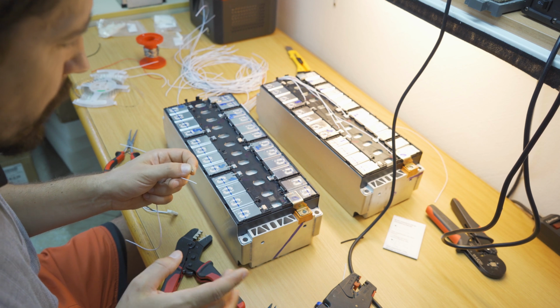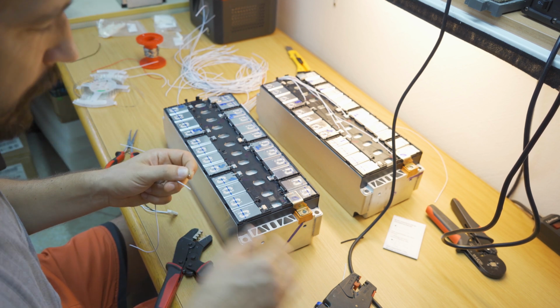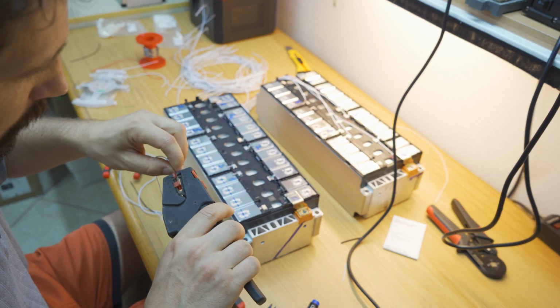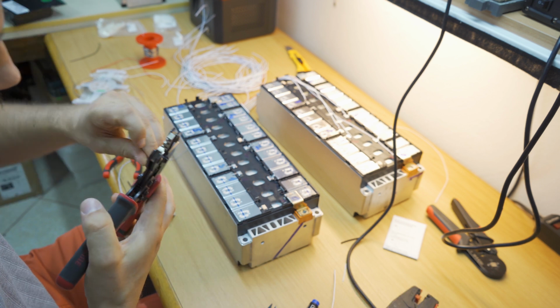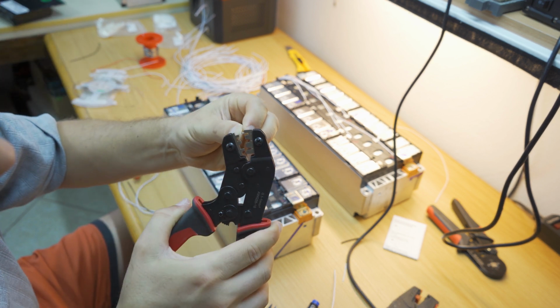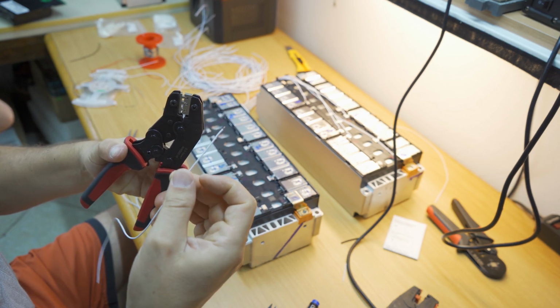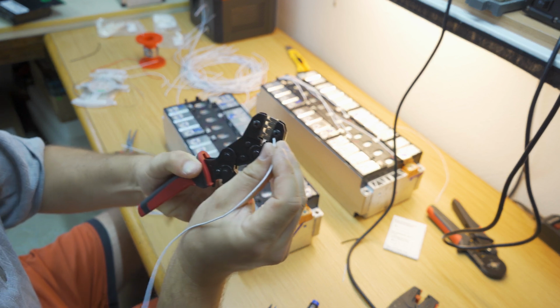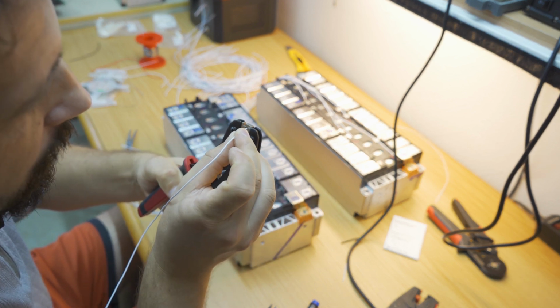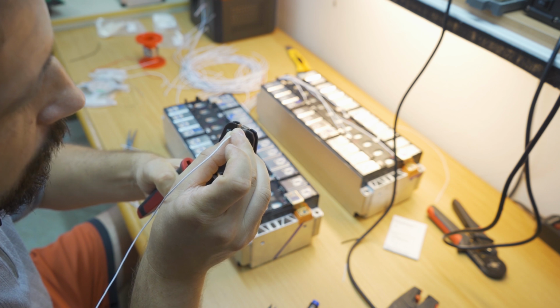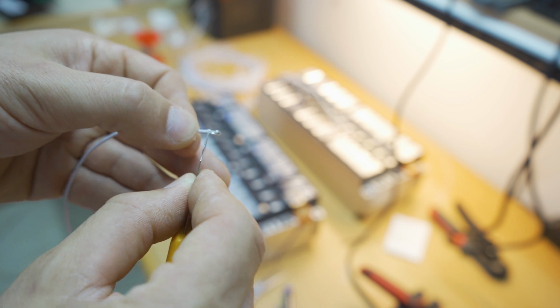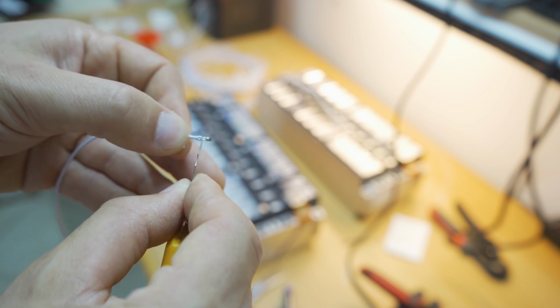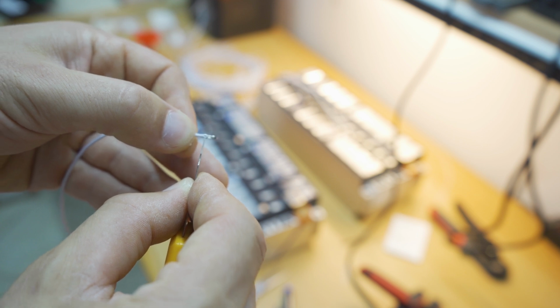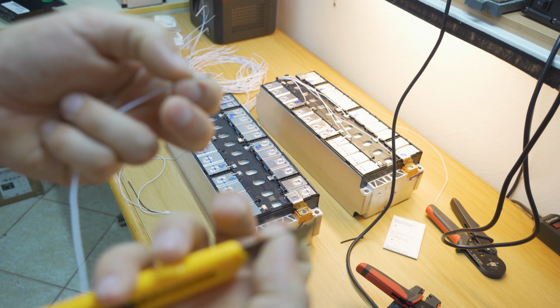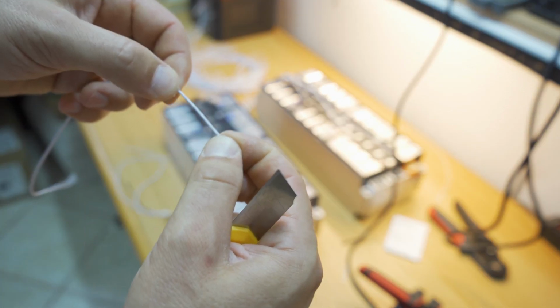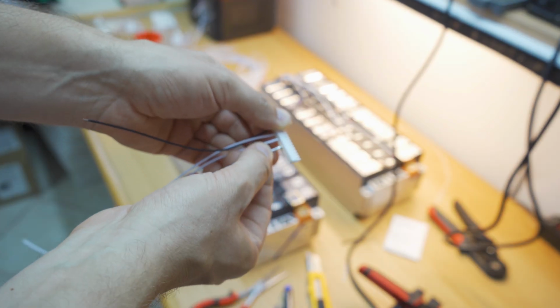So now I'm gonna show you how to properly crimp a wire so that it holds tight. First you need to remove the insulation, not too much and not too little. And the pin goes now into this crimping tool. You just take the wire on this side and then put it into the pin. And just squeeze. The proper crimping is that you have the insulation up to here so that these first two spikes go into the insulation so that it holds tight. And now it is fitting tight and you can't remove it. And now you just push it into the connector.